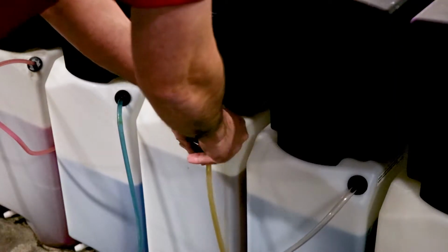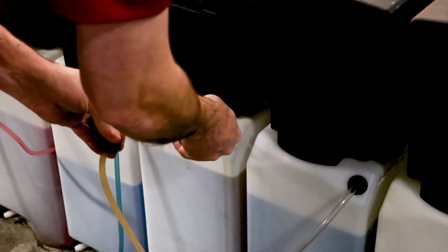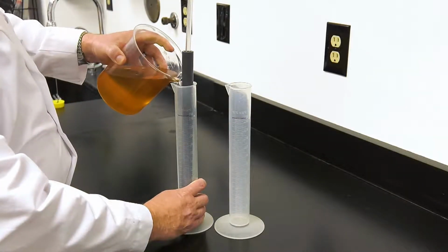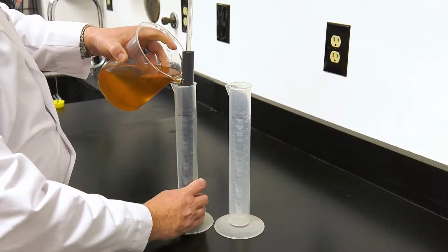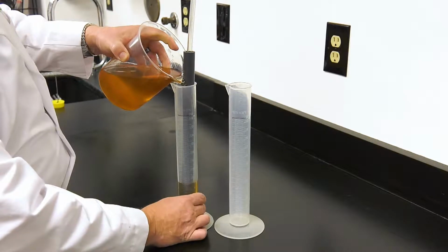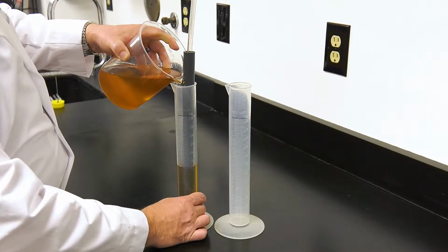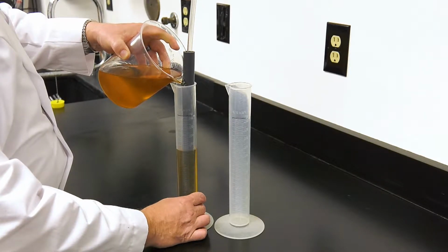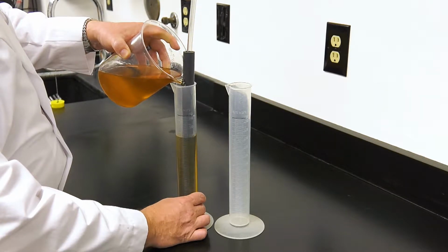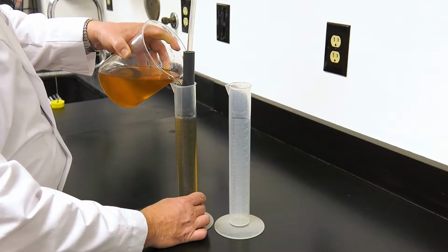If possible, take the manifold foot valve out of the existing chemical drum or tank and place it in the cylinder on the left. If that is not possible, remove the existing chemical line and replace it with a new chemical line and foot valve. If the line is empty, activate the test function to prime the line. If this is not done, chemical usage measurements will be much greater than actual.